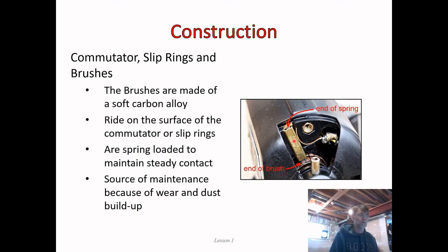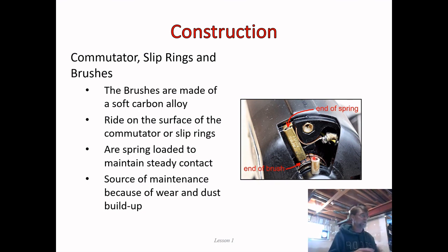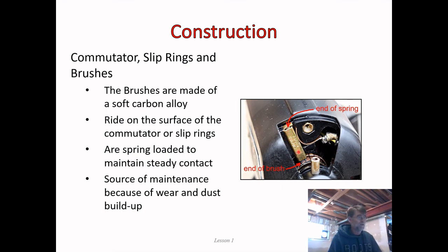The commutator and slip rings provide an electrical connection between the fixed external wiring and the rotating armature windings. We can't just hardwire the terminal leads to the coil ends because as soon as it starts to spin it would coil up and break. The brushes are mounted to the chassis so they don't rotate, but they make contact with the rotating commutator. They are made of a soft carbon alloy, are spring-loaded to maintain steady contact, and are a source of scheduled maintenance because they wear down and leave dust.